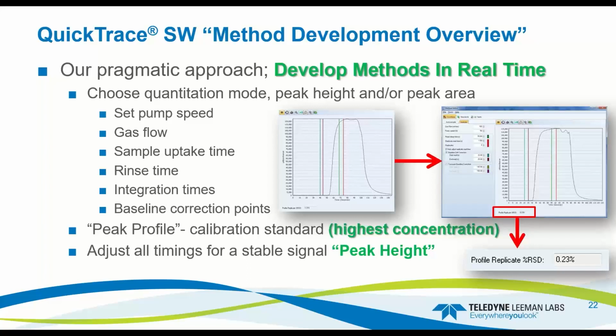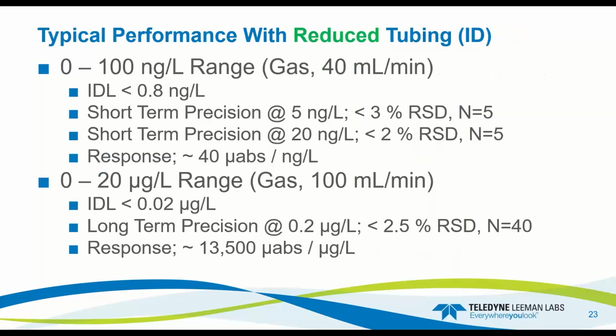It takes literally less than 2 minutes to develop a method. You put your pump tubing on, and then, assuming it's been conditioned, you go in and create your standards. You read your high standard, which is going to be your worst case scenario. You dial in your timing, everything for the peak plateau or peak area if you're doing that as well. And then it'll give you your percent RSD for the plateau. And then you're ready to go on to running standards and running your method.